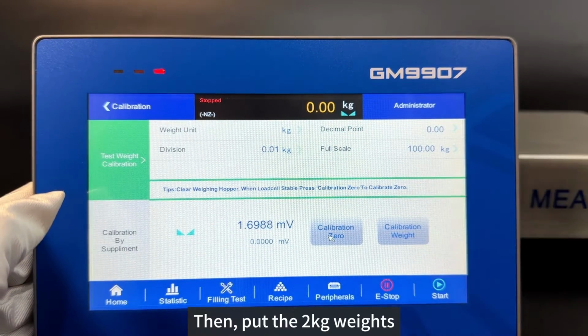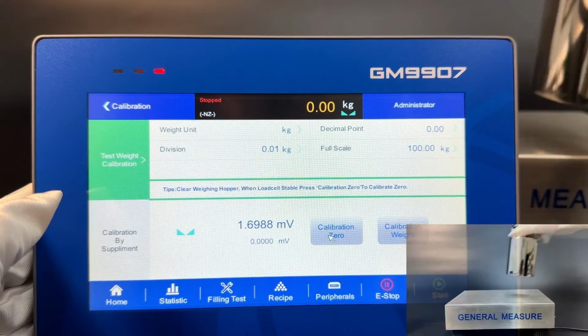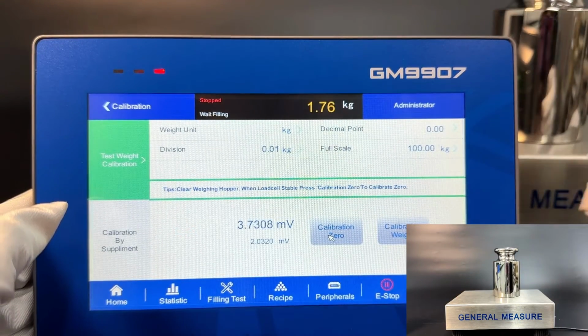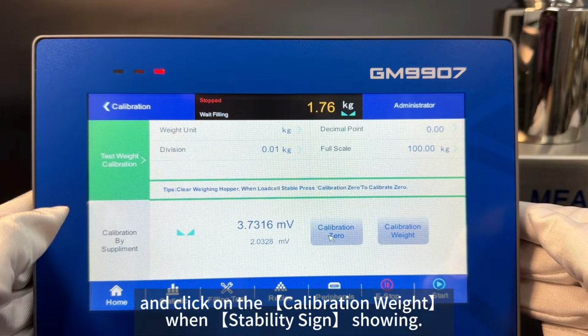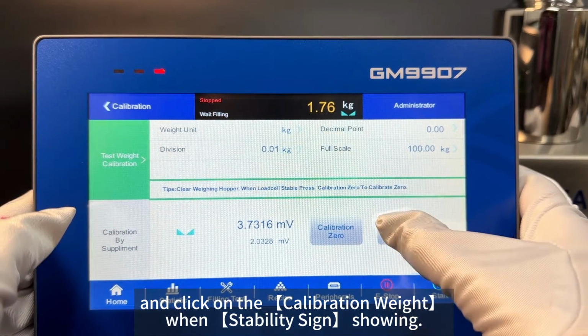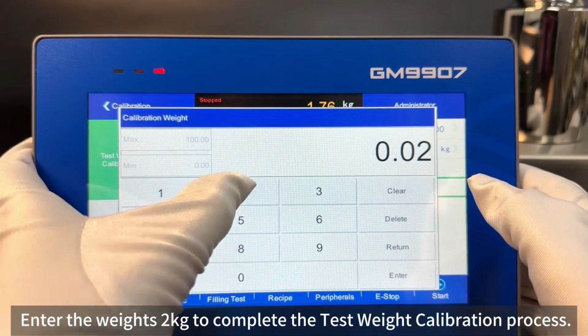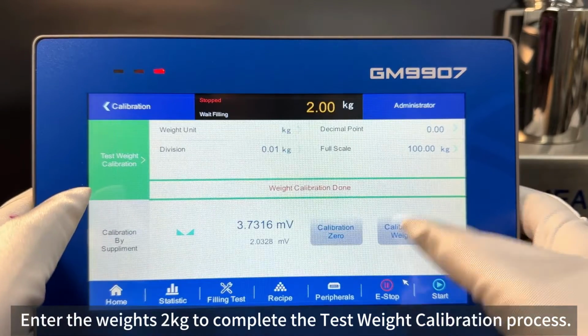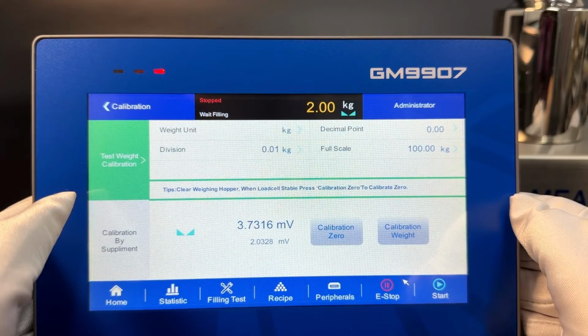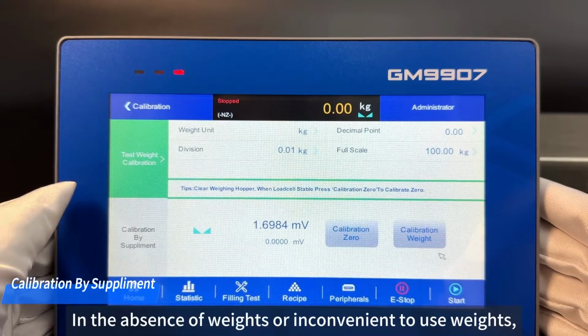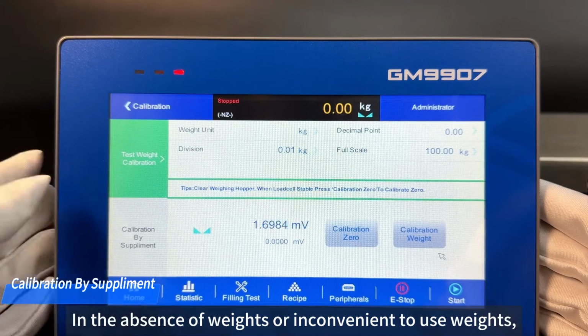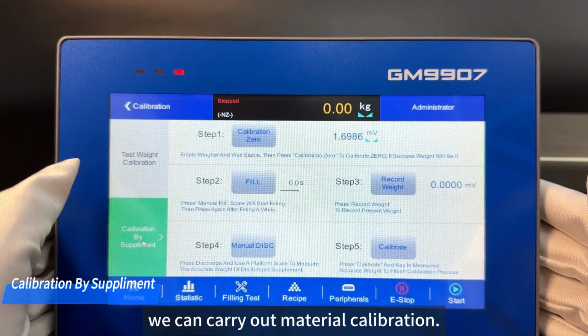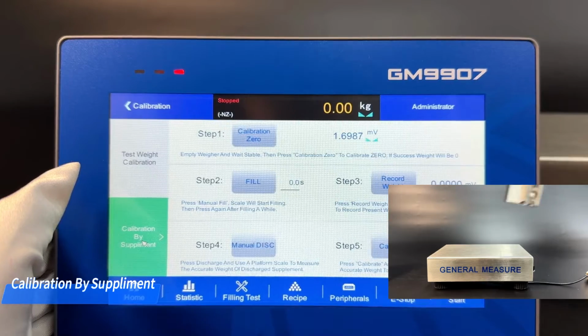Then, put the 2 kg weights on and click on calibration weight when the stability sign is showing. Enter the weight, 2 kg, to complete the test weight calibration process. In the absence of weights, or when it is inconvenient to use weights, we can carry out material calibration.